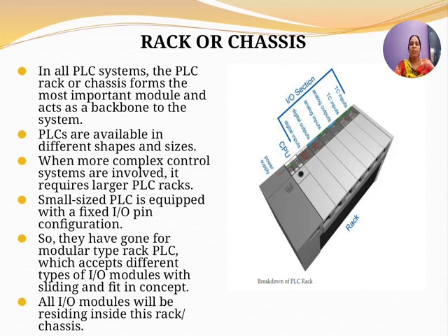The PLCs are available in different sizes and shapes. When more complex control systems are involved, it requires larger PLC racks. Small size PLCs are equipped with a fixed I/O pin configuration. So these racks and chassis also have their own configuration. They have gone for a modular type rack PLC, which accepts different types of input output modules with a slide and fit-in concept. All input output modules will be residing inside the rack chassis.